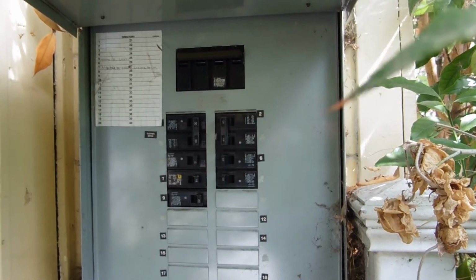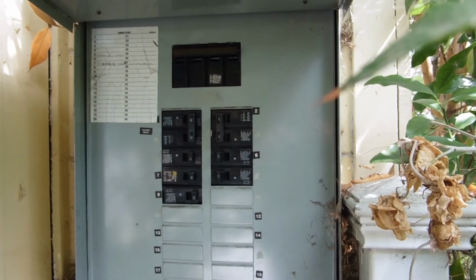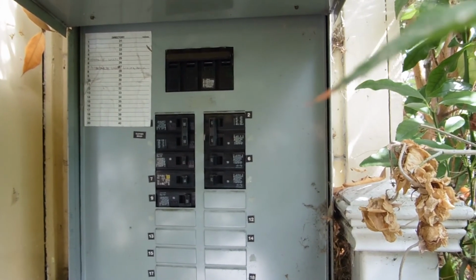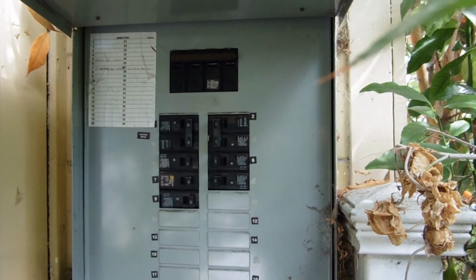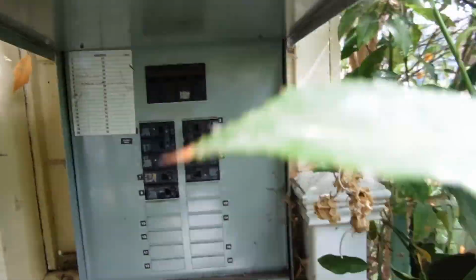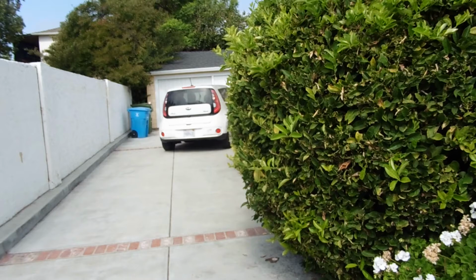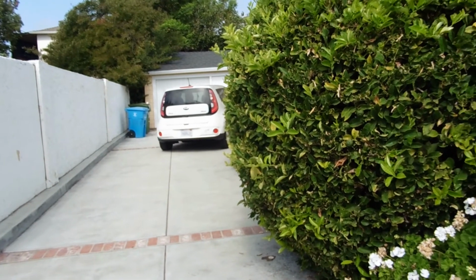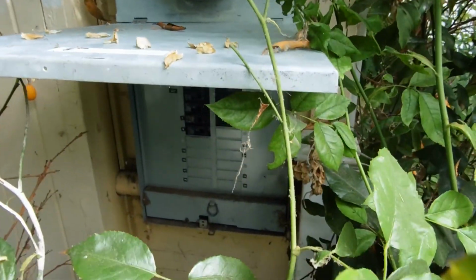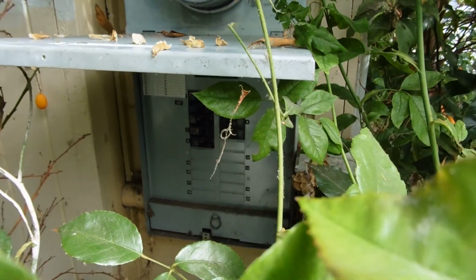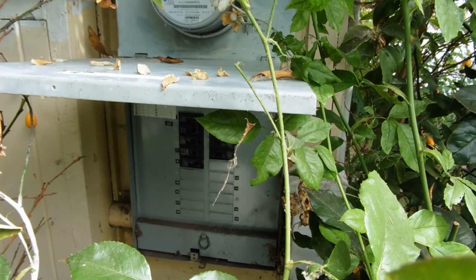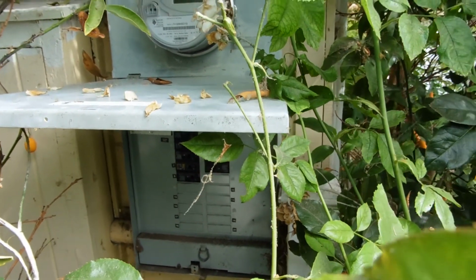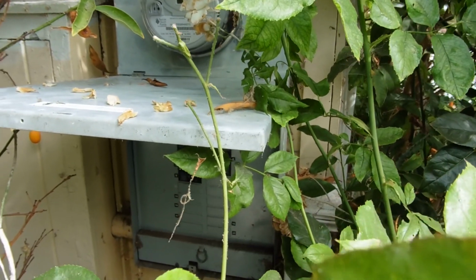So say the one at the top is 200 amps, which it might be. That means there would be 40 amps of service capacity remaining. The reason this is important is that if you're talking about adding a full powered charging station for an electric car, you're going to be adding electricity usage to your house. To do that, you need capacity in the service panel, which again is way back here behind all this. As I just calculated, possibly this service panel has 40 amps of remaining capacity. So that would be enough for one 32 amp or 6 kilowatt charging station.